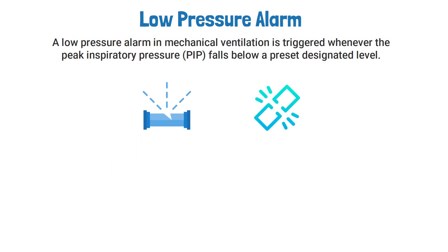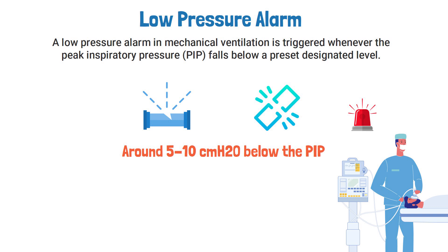The preset low pressure level for this alarm is typically set around 5 to 10 centimeters of water pressure below the peak inspiratory pressure. If this alarm is triggered, the respiratory therapist must first ensure that the patient is being ventilated. If the cause of the alarm is unknown, the patient should be manually ventilated until the source of the leak is identified.